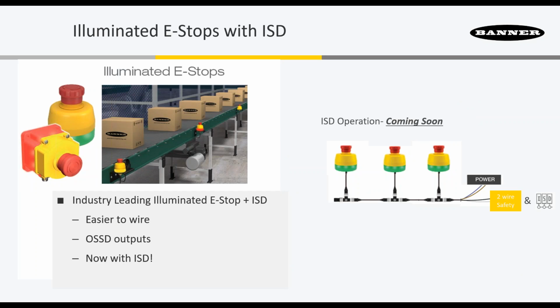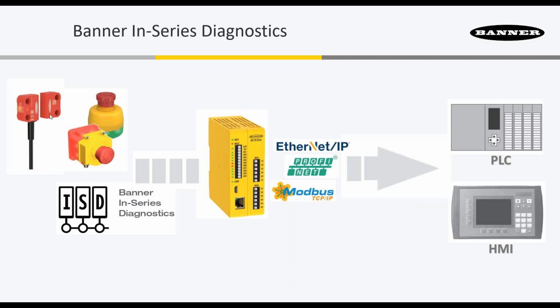Someone is asking if ISD is based on IO-Link, and the answer to that is no. It's an entirely different protocol. That's correct. Yeah. So this is a Banner protocol. What's really cool about this is the devices, the RFID switches and the E-Stops. The 2 wires that come into the SE10 are OSSD outputs, the same OSSD outputs you'd have from a light curtain. But what we do is we send a proprietary Banner protocol that rides on the OSSD line, and the SE10 is able to interpret the data from that and turn it into useful information that you can use to troubleshoot the system. So it's a really neat system. There's no extra wires required. It uses your same OSSD outputs.